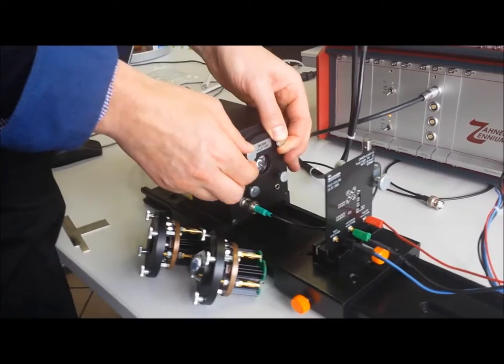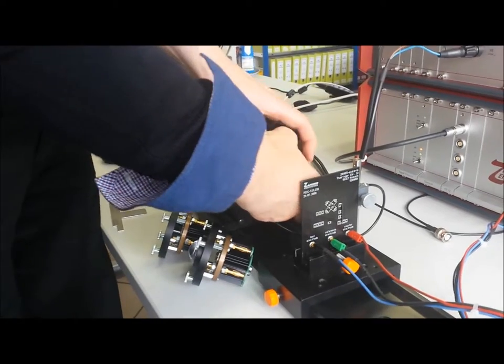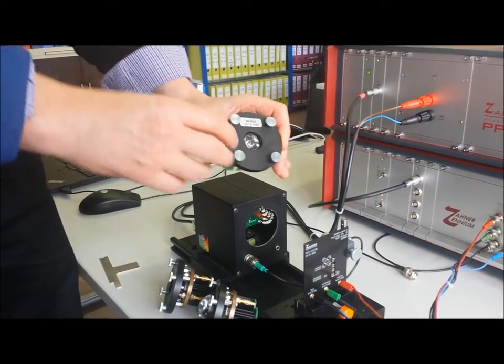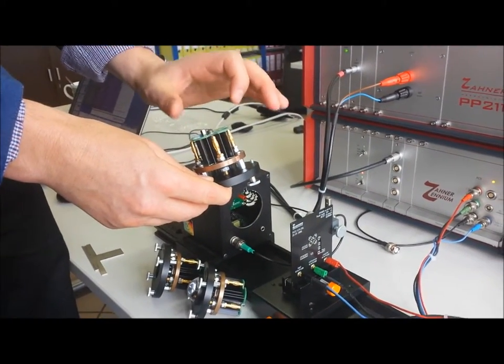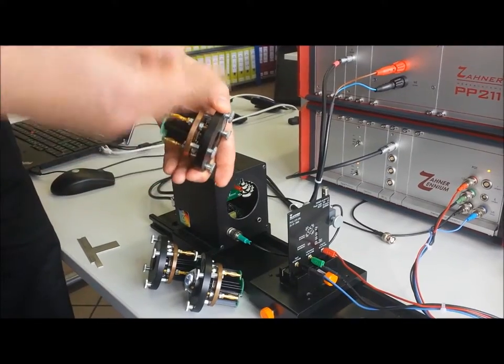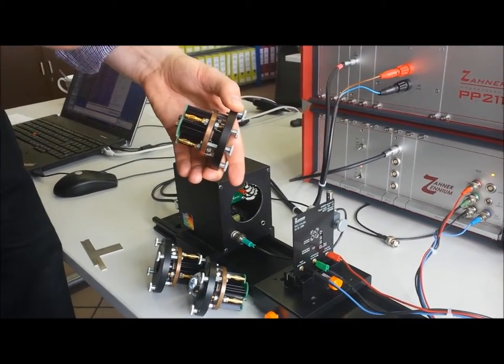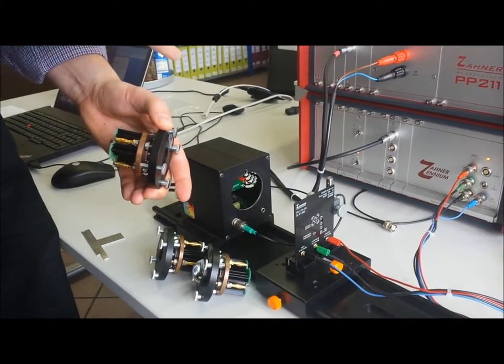If you want to change the light source, it's very simple. You can just pull these out. They're smart, so there's a communication between this device and the box, and all the calibration factors and parameters are transferred and read by the software.